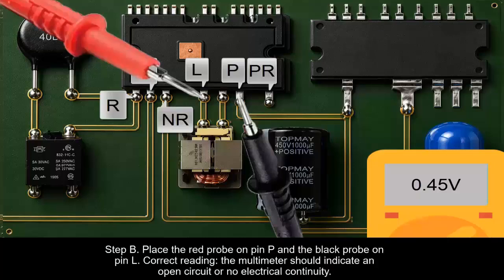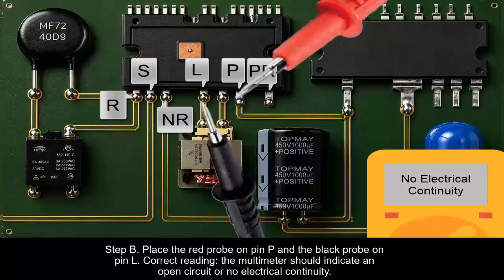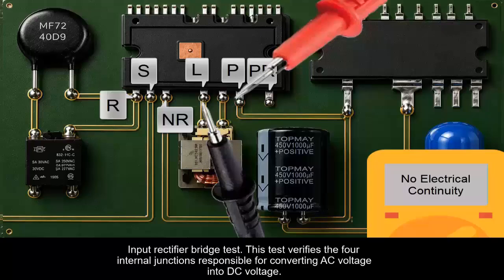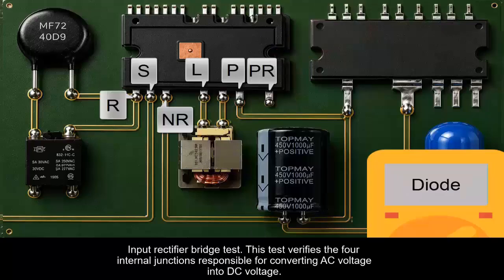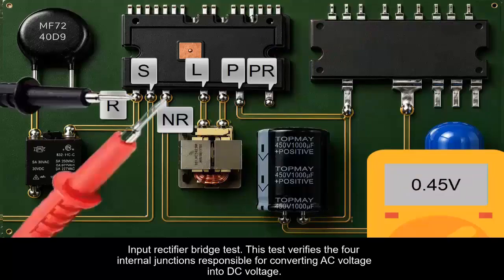Step B. Place the red probe on pin P and the black probe on pin L. Correct reading: the multimeter should indicate an open circuit or no electrical continuity. Input rectifier bridge test. This test verifies the 4 internal junctions responsible for converting AC voltage into DC voltage.